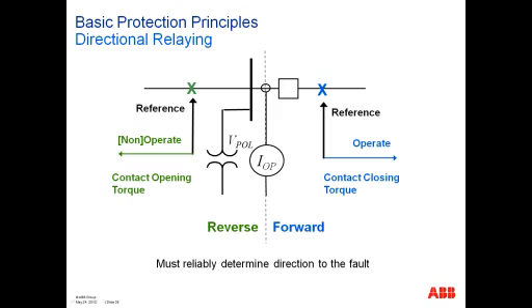Directional relaying. What directional relaying requires is some type of what's referred to as polarization, but it's a reference quantity that maintains its relative direction regardless of if the fault is on the upstream or downstream or high side or low side. Regardless of where the fault is located, the phasor of that polarizing quantity is always at the same angle. And then you have an operate quantity, which would be in one case here shown as forward. It would show the fault as forward when compared to the reference quantity, or it would show the fault as reverse when compared to the reference quantity. So that's the key for directional relaying.